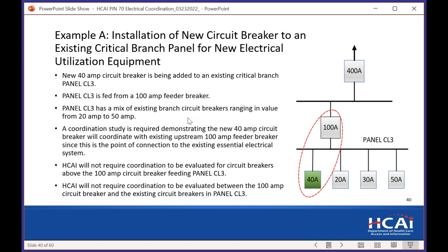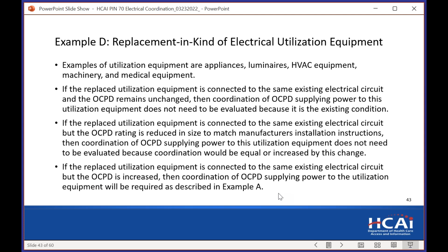Replacement in kind, we talked about this for utilization equipment. Again, if you're replacing utilization equipment and you're connecting to the same existing circuit and the OCPD remains unchanged, we don't require coordination. If you reduce the size of the overcurrent protection device, still connected to the same panel, you do not have to demonstrate coordination. But if you're increasing the size of the OCPD or you're connecting it to a new source of power, then you have to coordinate.